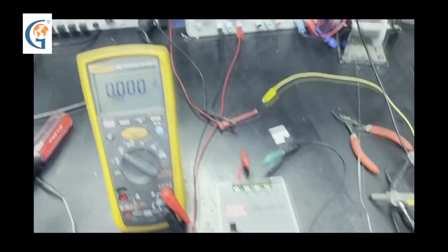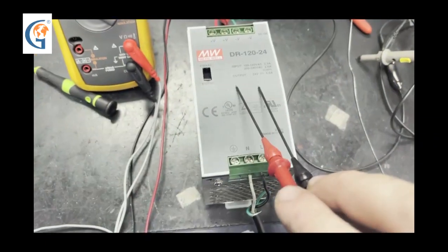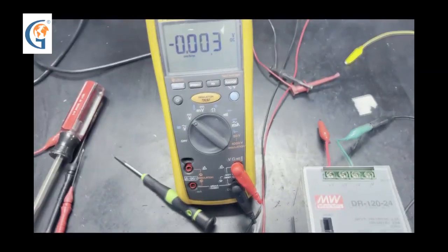To put under load, we'll power off the supply and wait until the bus caps drop all voltage. Now that it's under 1 volt, we will go ahead and hook up our Dyna load.